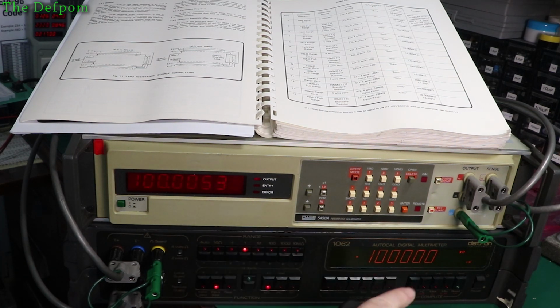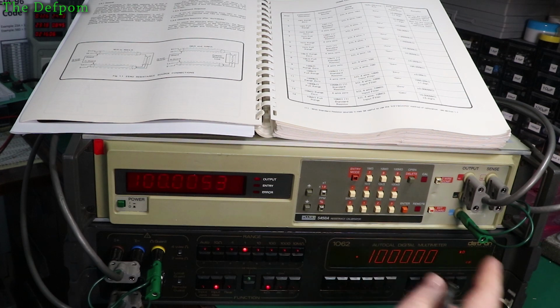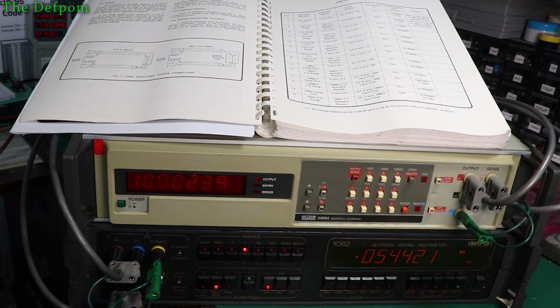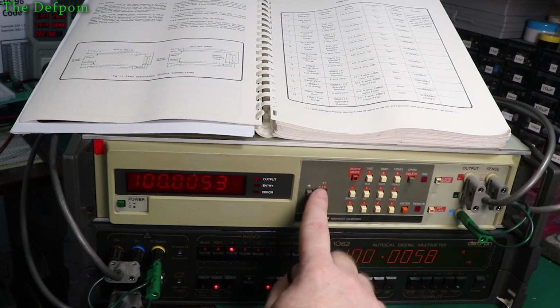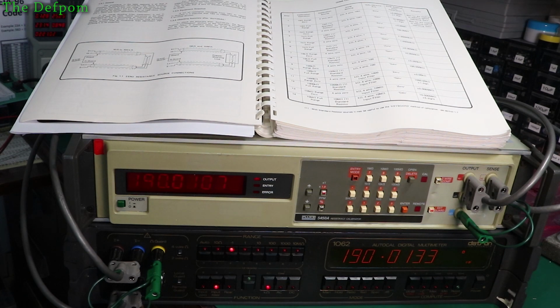Let's take the 1.9 off. So this is slightly low. One side's slightly high, one side's slightly low, so the linearity aspect of it isn't quite right. The middle is right, the bottom end is a bit low, top end's reading a bit high. But you think with the zeroing set up, that shouldn't really happen. Yeah, you have to wonder a little bit. So let's do 10 ohms. That's reading slightly low there, as expected. Right, slightly low there. 100 ohms should be right. Pretty much is. If I do 190, I bet that's reading slightly high. It is. About 26, 27 counts high. See a theme there?